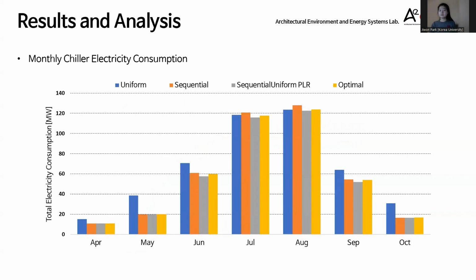The following graph represents the monthly cooling energy consumption for each load distribution algorithm when operating the building with four chillers. It can be observed that during the transitional months of April, May, September, and October, the uniform algorithm consumed the most cooling energy. On the other hand, during the hot months of July and August, the sequential algorithm consumed the highest amount of cooling energy. Throughout the year, the sequential uniform PLR algorithm consumed the least cooling energy.